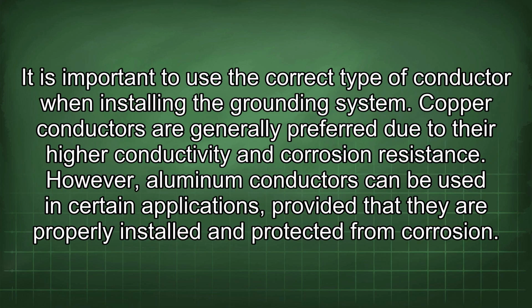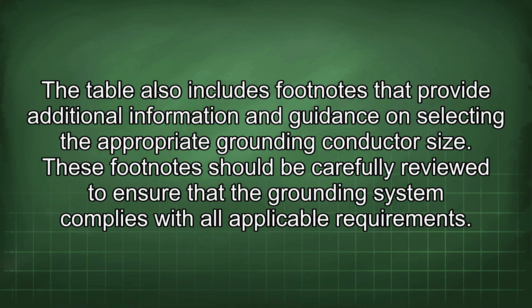It is important to use the correct type of conductor when installing the grounding system. Copper conductors are generally preferred due to their high conductivity and corrosion resistance. However, aluminum conductors can be used in certain applications, provided that they are properly installed and protected from corrosion. The table also includes footnotes that provide additional information and guidance on selecting the appropriate grounding conductor size. These footnotes should be carefully reviewed to ensure that the grounding system complies with all applicable requirements.